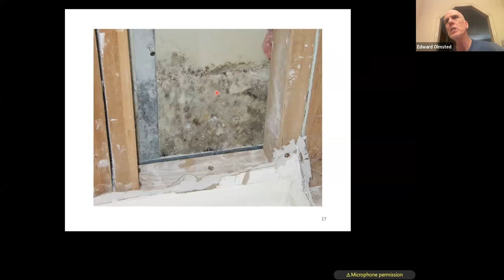Oh, okay. Condensation — this is on a chilled water line. We see this in the summer. Sometimes buildings will upgrade their air conditioning, put new chillers in, and the chilled water goes from being 45 degrees to 40 degrees. The insulation no longer is sufficient, and it gets cold on the outer part of the insulation, which becomes a condensing surface — a cold condensing surface — and then you get enough condensation.